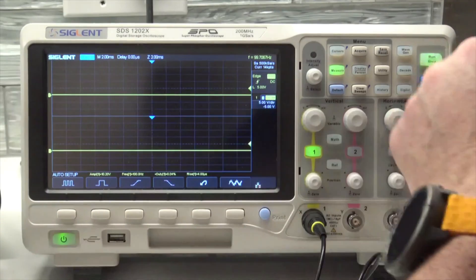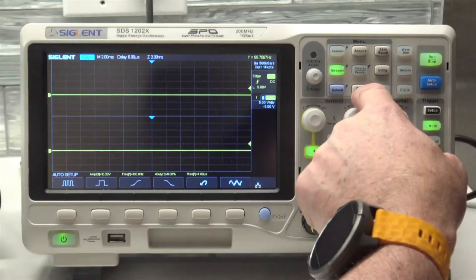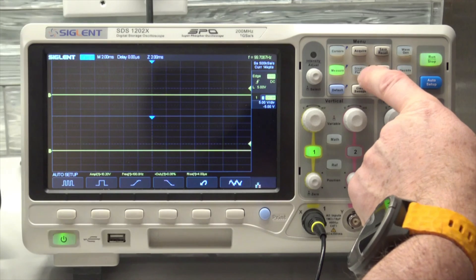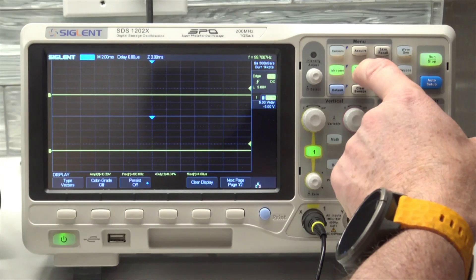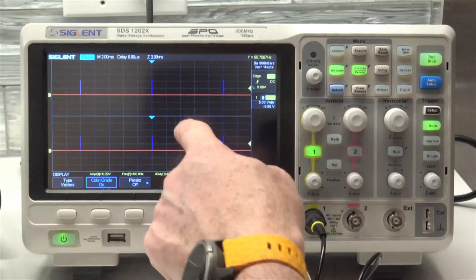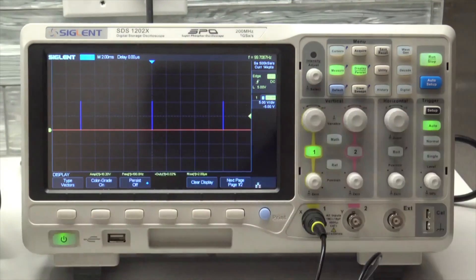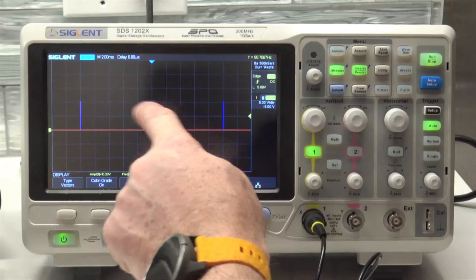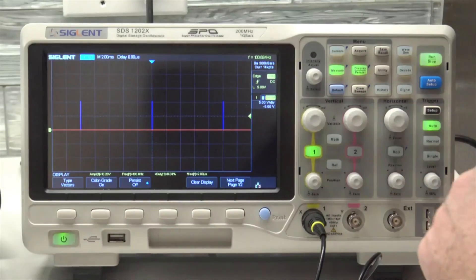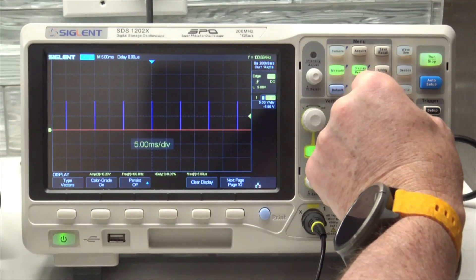When you're having a hard time seeing these little waveforms, one way to make it easier is to come to your display button and turn on your color grading. Now you can see blue, blue, blue, and our red line, and I can see more pulses.